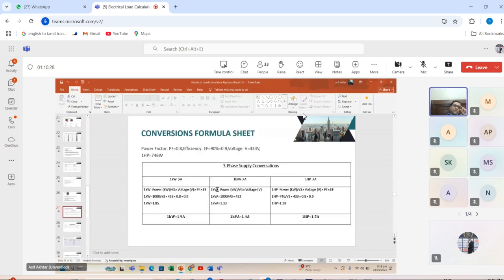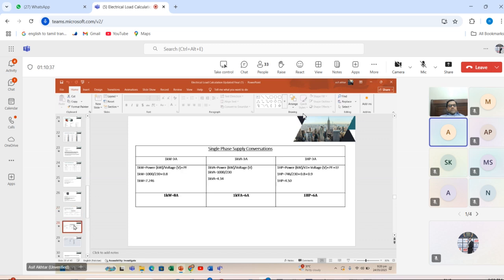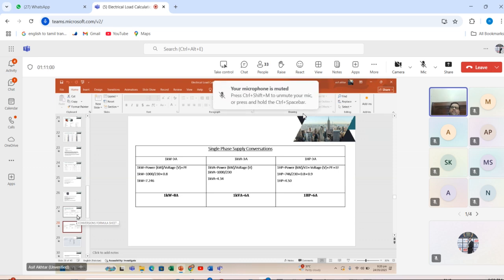This is the conversion formula which I have discussed with you. Here I have a question regarding selecting ACB: whether we select a 3-pole ACB or a 4-pole ACB. Basically, my advice is to use a 4-pole ACB so that in case of any issue the neutral can be disconnected. You can use a 3-pole ACB also, but my suggestion is to use a 4-pole ACB from the safety point of view.